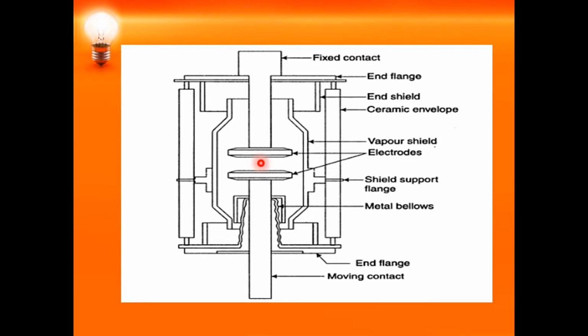The contact material of this vacuum circuit breaker should have a high electrical conductivity so as to pass the normal load currents, that is, the electrodes. The contact material should have low resistance and high density. It should possess a high thermal conductivity so as to dissipate the large heat generated during arcing, and the material should be able to withstand high arcs and have a low current chopping level.